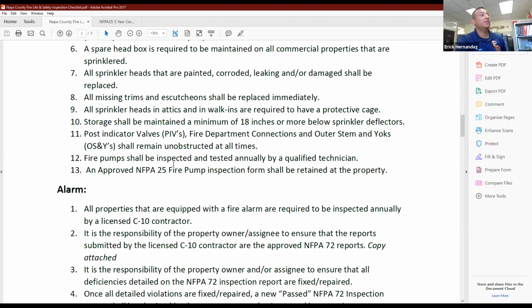So that's another thing. One of the things that I highly recommend is, as property managers, just have a monthly internal inspection, where you walk the property or assign someone to do a couple things. Look at all your sprinkler heads. Just do a visual. Look at your sprinkler heads and make sure that there's no leakage. There's no paint over any of the sprinkler heads or any of the compartments. Like the escutcheon is the ring that goes around the sprinkler head.